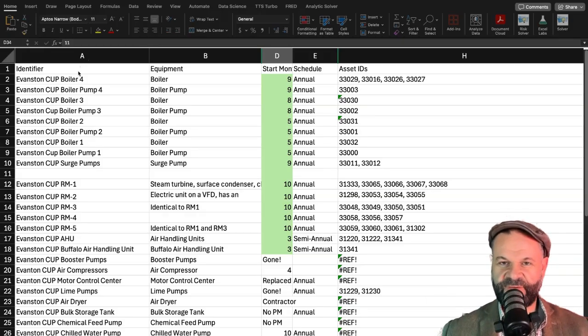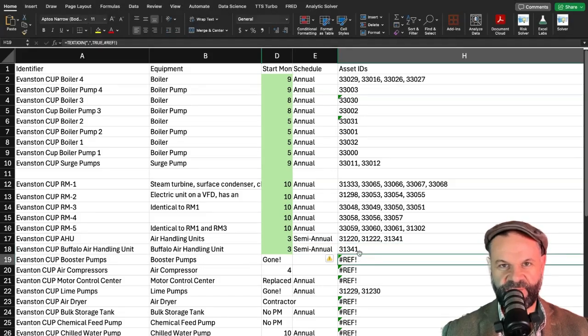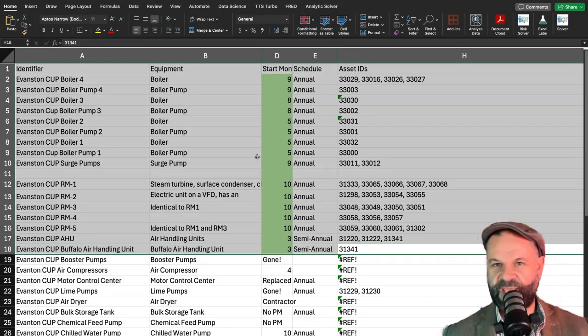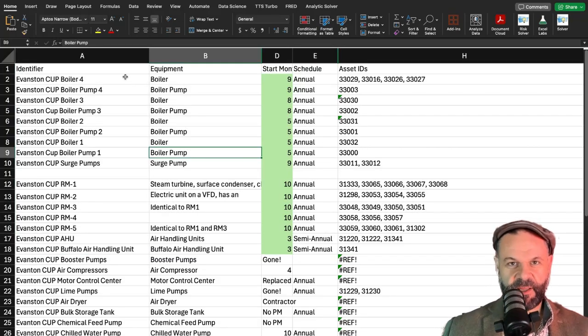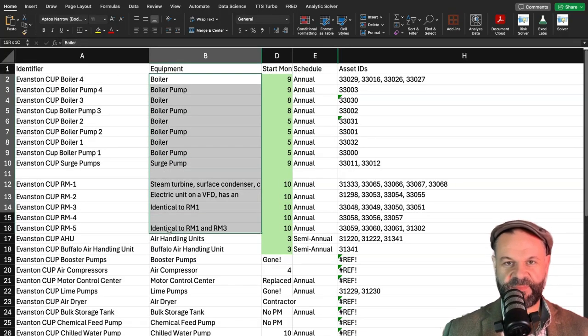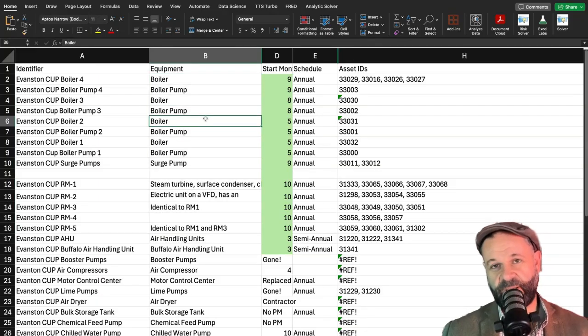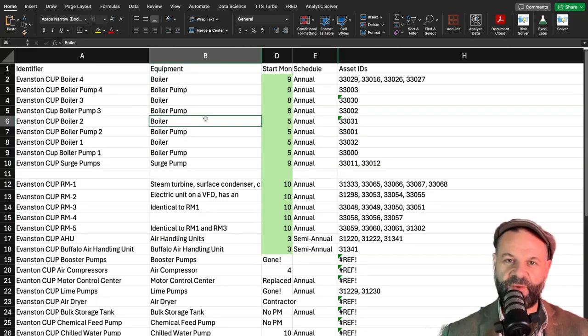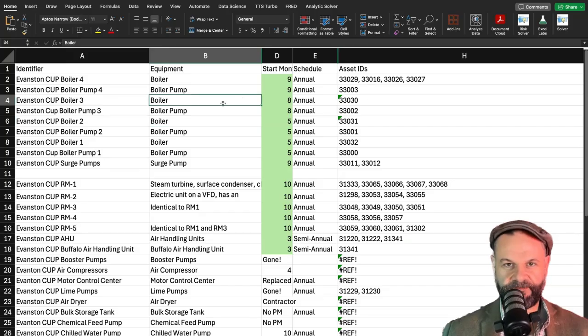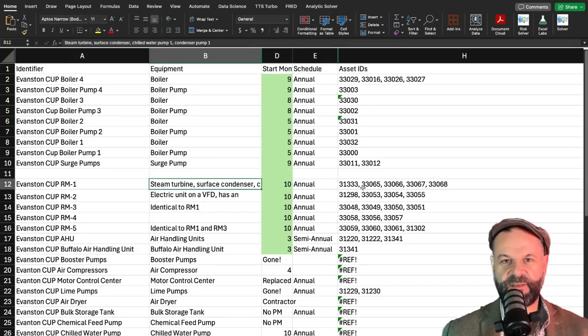Column A, identifier, is a grouping of equipment that will go into a single PM. From row 2 to row 18, or 21, this is the part I've worked out so far, based on conversations I had with the technicians in the plants who have to get input from the actual workers. Column B is the main equipment type, so the boiler here might have a pump, might have some water softening equipment, but overall this is all just the agglomerated equipment around that piece.